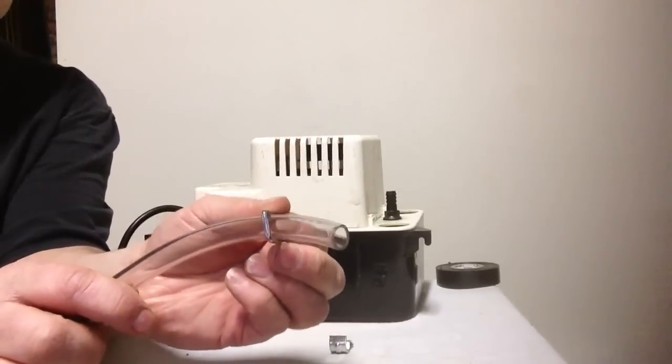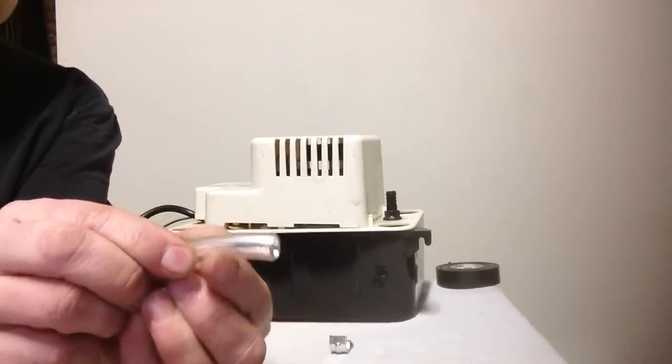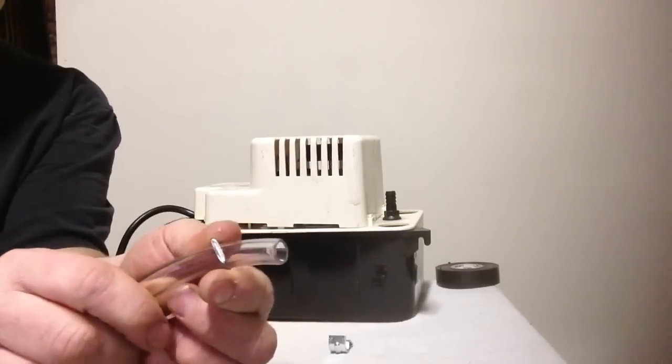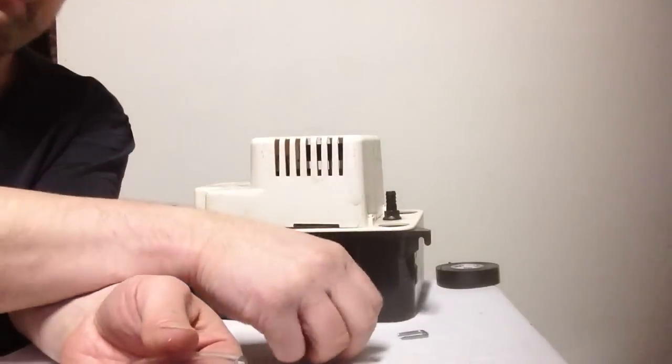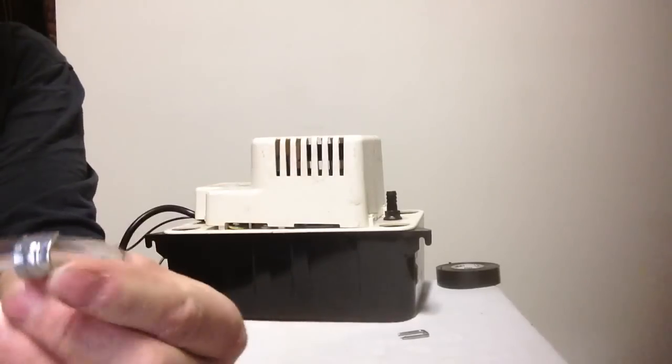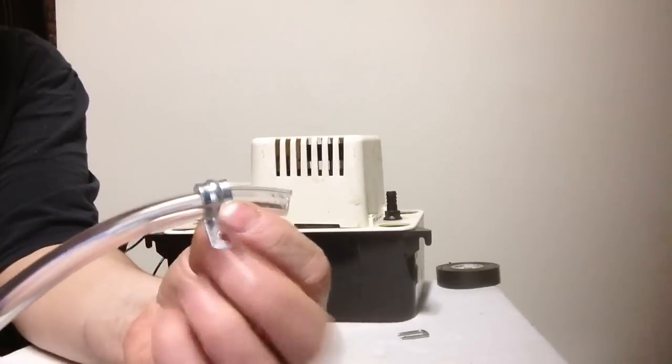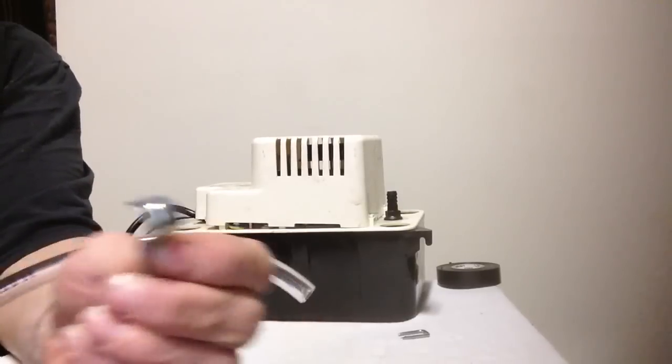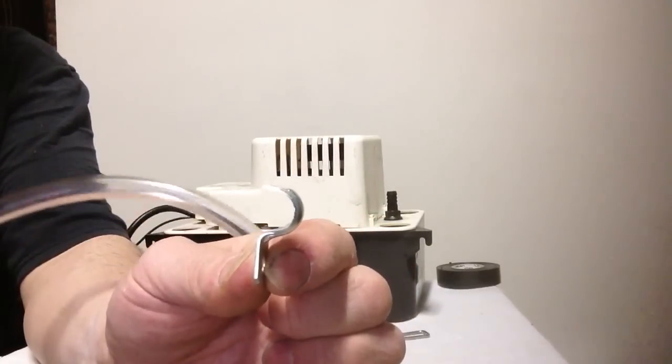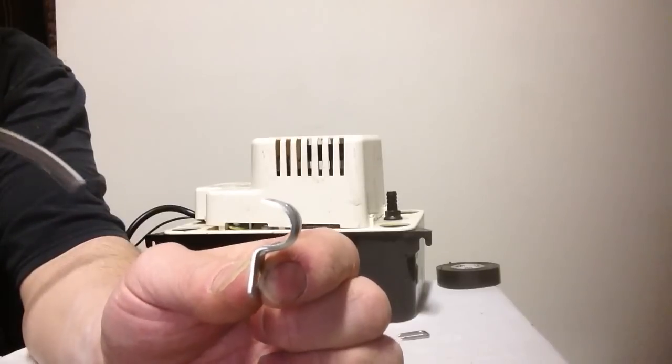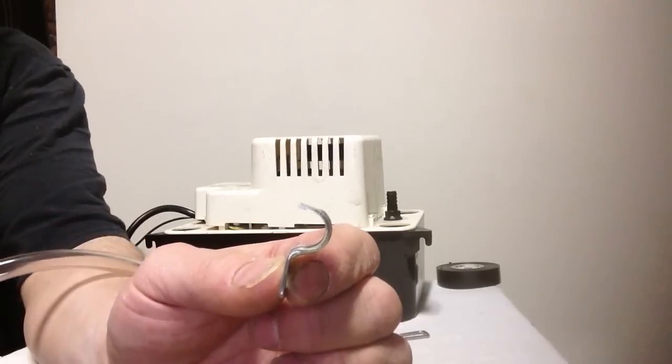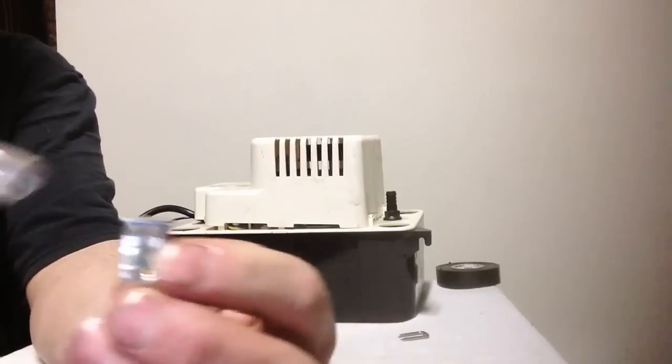Wire staples usually end up compressing the tube and it just doesn't work out too well. You want to get a clamp and clamp that right on your tubing and screw that into your joist. These work a lot better. You probably get these in the electrical department. Stay away from the staples and you can attach that on there and screw it in.